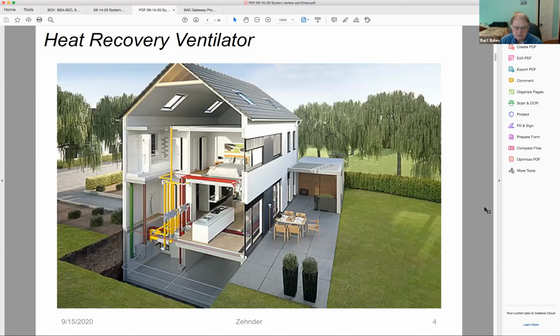Okay, this is of course only a residential application, but the principle's the same. You're intentionally bringing air to all areas of the building for ventilation, which is for proper health. And then you're exhausting the same amount of air intentionally, otherwise having a very tight structure. And you're recovering the thermal energy that's leaving the building and preheating the air coming into the building.